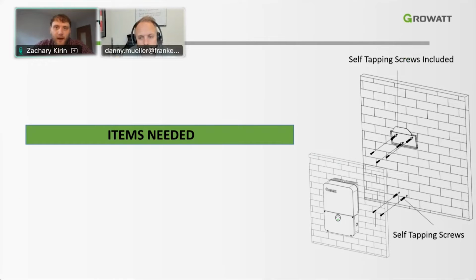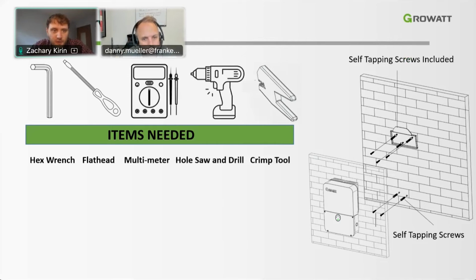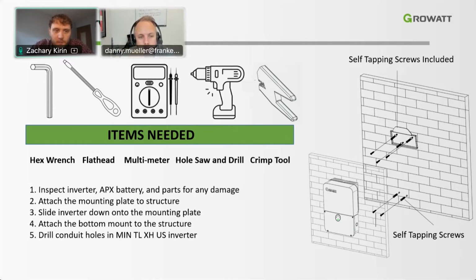Excellent. So what are some items that you need to install the inverter for the first time? What are some items that you're going to need? Well, the very first part is you'll need a hex wrench, flathead screwdriver, a multimeter, a hole saw, and a drill, and of course, a crimping tool as well. So before you mount the inverter, it's important to inspect the inverter, the APX battery, and any parts within the packaging for damage. There is no real issue with shipping damage that we have seen, but anything can happen in shipping.